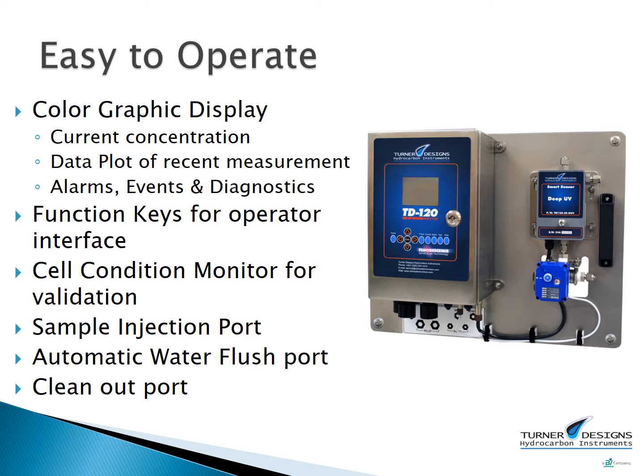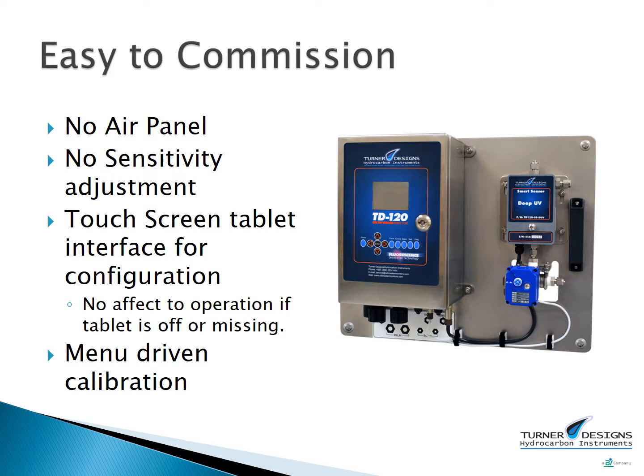Should cleaning be needed, a few options are available. First is the automatic water flush port, and the second is a manual clean out port on the top of the flow cell. A touch screen tablet is installed inside the TD120's enclosure for calibration and commissioning.